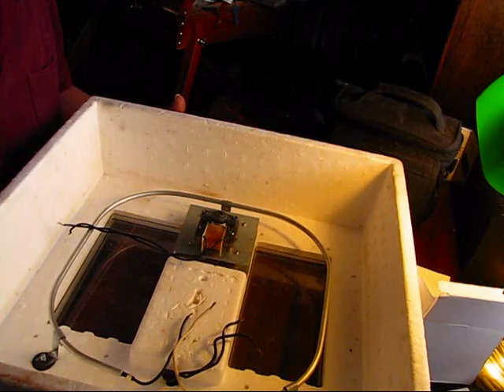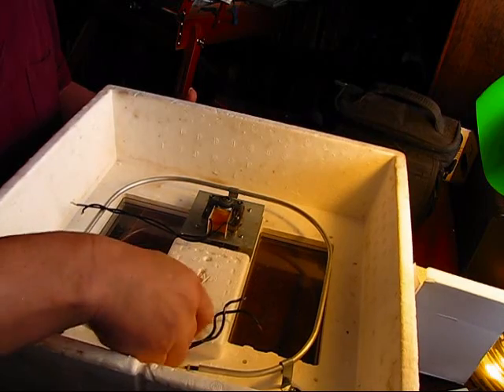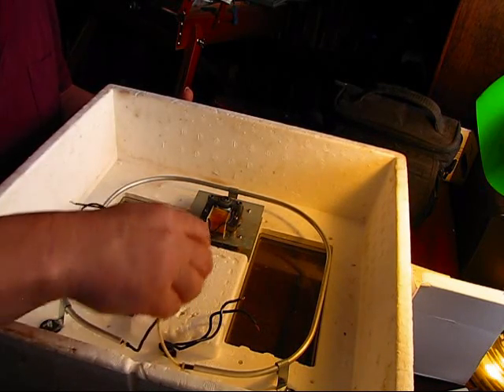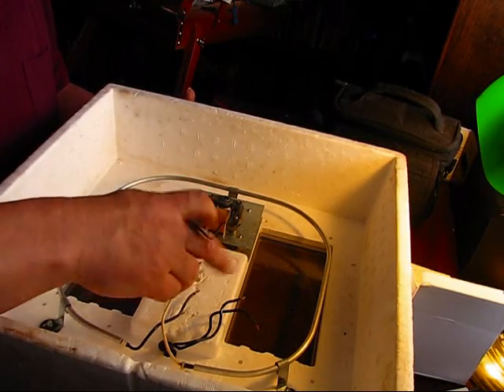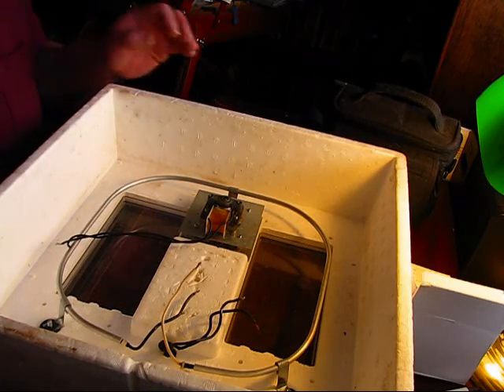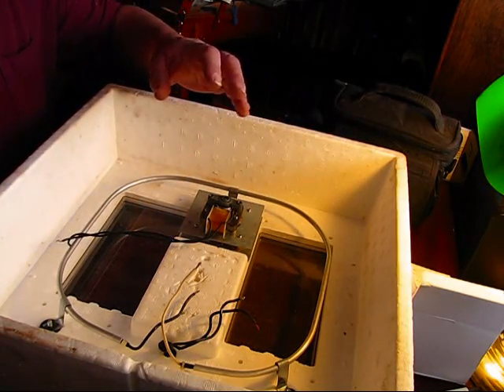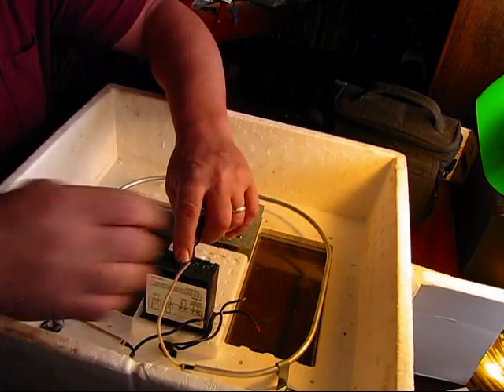First of all, I want to figure out the placement on where exactly I want to place that thermometer inside this incubator. So I'm going to note that there's the wires, the power cord that goes right here, the main element, the heating element wires are right here, and then these are the fan wires that are right here. So I've decided I'm going to place this thermometer right about here.